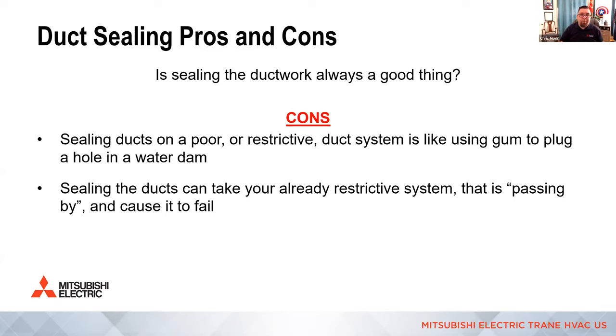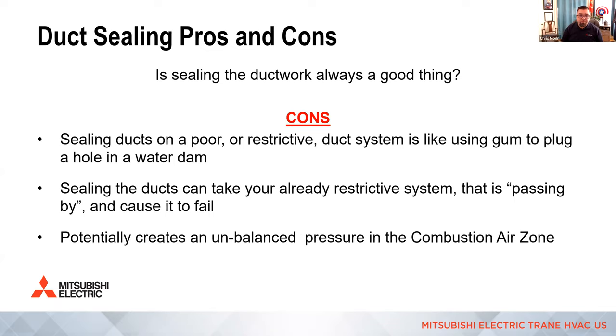It's going to start to bypass things and cause systems to fail if we have a really restrictive return, let's say, like I was talking about before, the dirt could just go right through or around the filter. And obviously, it creates unbalanced pressures in what could be a combustion appliance zone in a basement. So if we seal up everything and we start to pull more air through the holes at the return in the basement, we could depressurize that combustion appliance zone enough to, let's say, pull air back from an atmospheric water heater or something like that. We have to be careful.